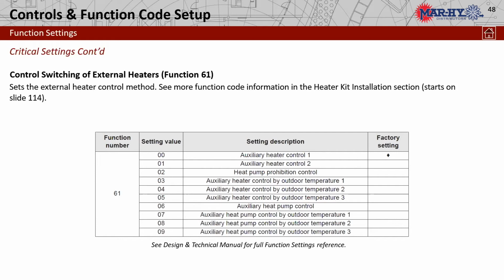Basically, outdoor limitations. We're going to set an outdoor temp that no strip heat beyond this point. And then if we do get to the point where we need strip heat, we're going to set a differential off of set point within the thermostat of when the strip heat will energize. And I've tried to go through this so it would be very conventional, like we would see in a standard heat pump system, meaning, 35-degree heat strip lockout. Once you drop below 2 degrees past set point, we will energize the strip heaters, and then it will terminate within 1 degree of set point.